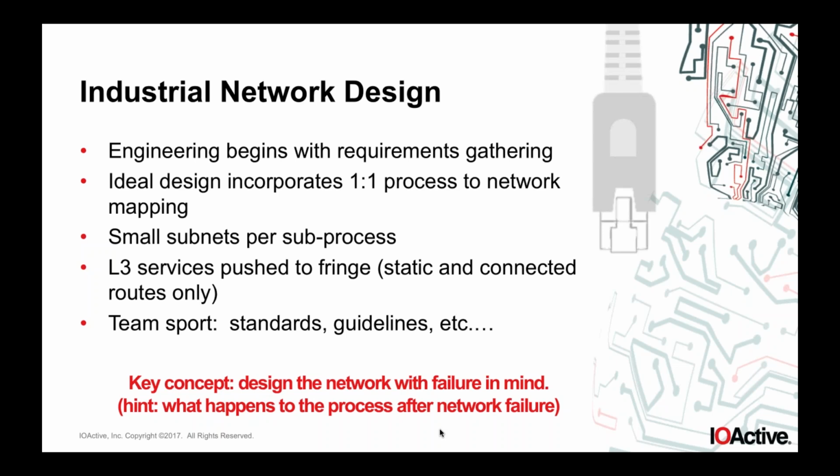The best part about pushing layer 3 services down closer to the actual endpoints and IO devices is that, should a security issue arise, you have the ability to dynamically spool up layer 3 ACLs to block whatever threat is inherent in the network. Now, it's a lot of engineering to block those by default, and that's one of the number one pushbacks we get, especially from a design and commissioning standpoint for these styles of infrastructure. But if you have the ability to do it, it at least gets you to a defensible position later when the event occurs.